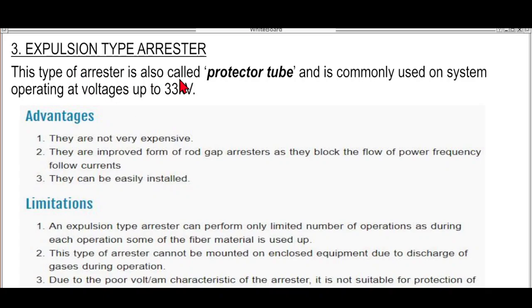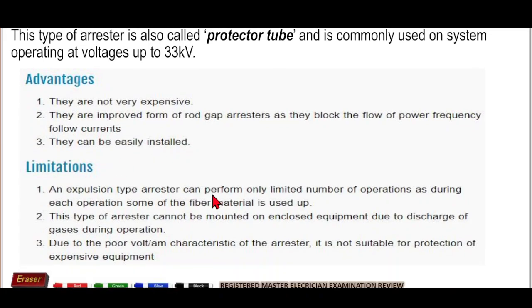Also called a protector tube, it is used up to 33 kilovolts. Their advantage is that they are not very expensive. They are improved versions of the rod gap and can be easily installed. The limitation is that they have a limited number of operations, meaning once struck by lightning, it will no longer be able to perform and will get damaged. It cannot be mounted on enclosed equipment due to discharge gases during operation, and due to the poor volt-ampere characteristics of the arrester, it is not suitable for protection of expensive equipment.